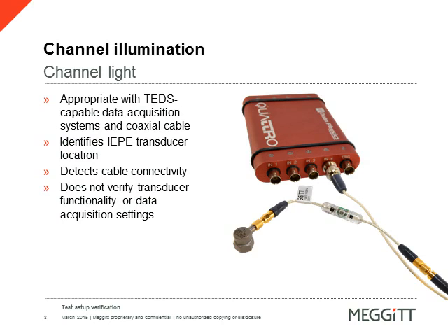For instance, in most large channel tests, all the same color wiring is used. A misplacement of a wire from position B to position C is very difficult to troubleshoot. This channel illumination method really helps out with that. However, this does not check the validity of the transducer itself. It's just an easy method to know which cable, which channel is connected to which sensor location.